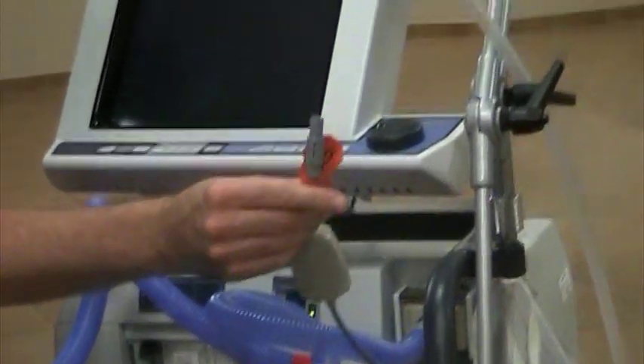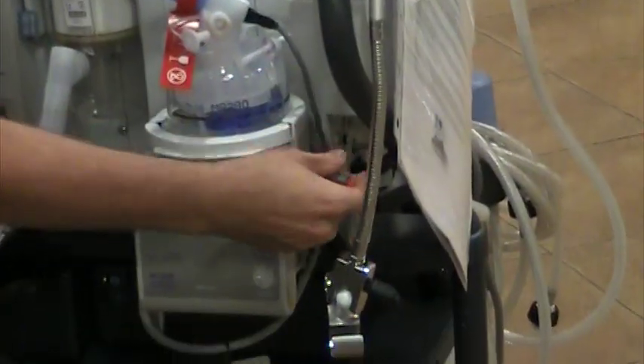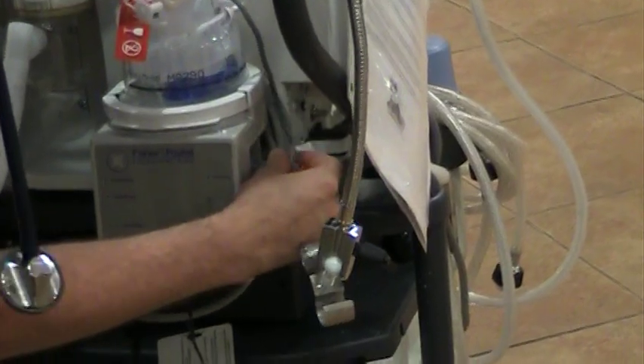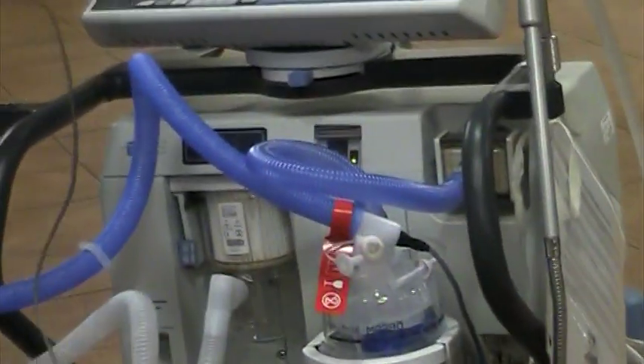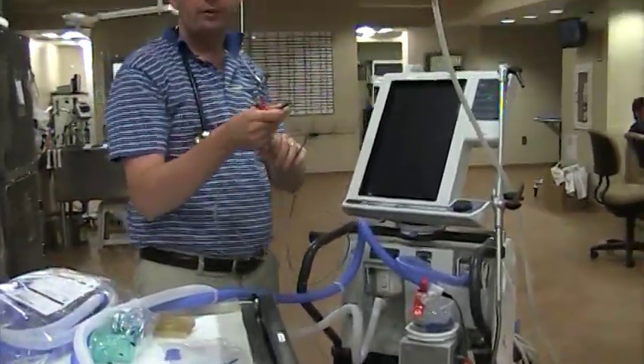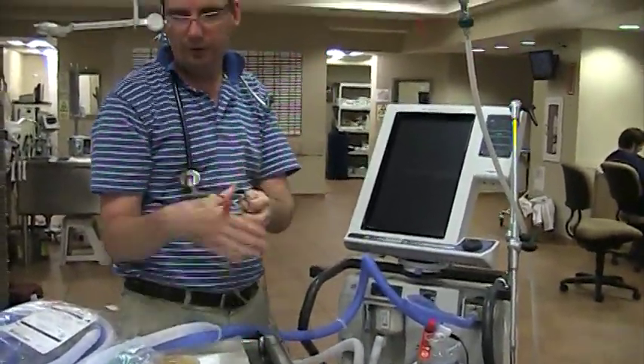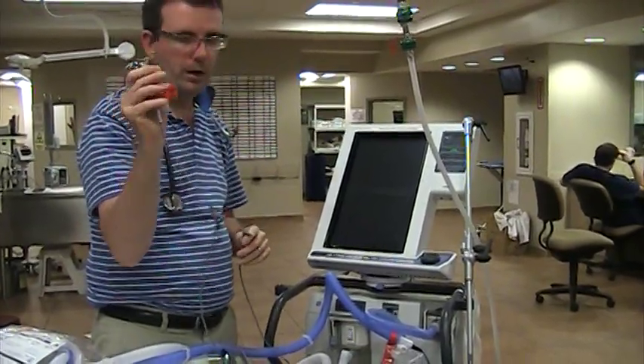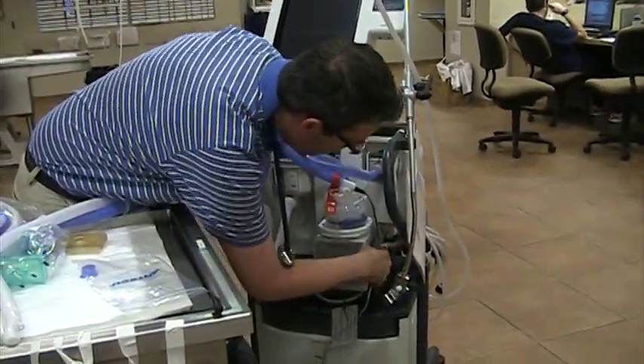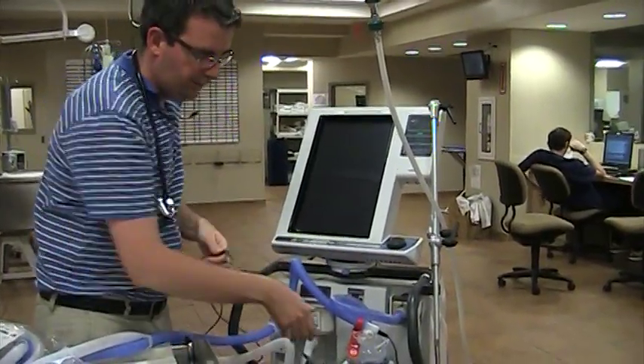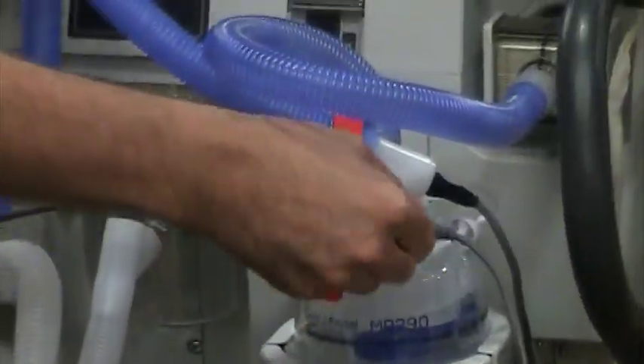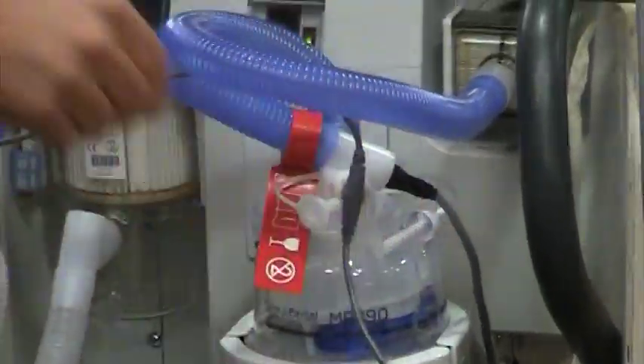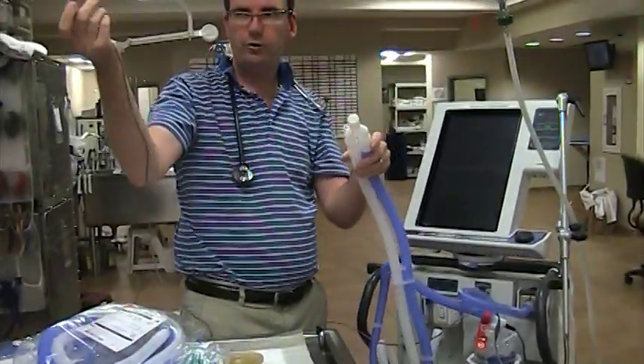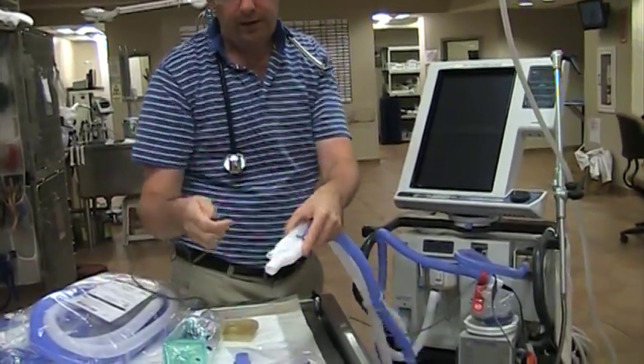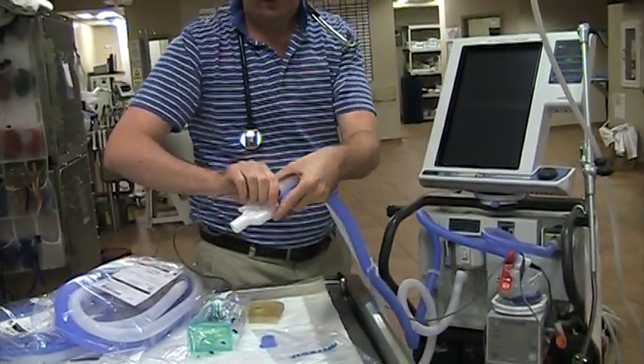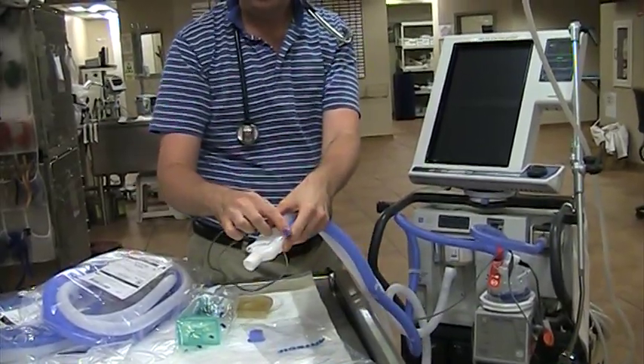And then here there's little black arrows. They just go into the top hole on the side of the humidifier there. This is the actual sensor, so it detects the temperature inside the tubing. So the gold part goes into the lower hole on the humidifier. And then the first little sensor goes right in here. You just twist it in. And then the second sensor, which is right at the end of the line, goes into this little hole right here. Not into the white hole, into the one where the blue cap is.